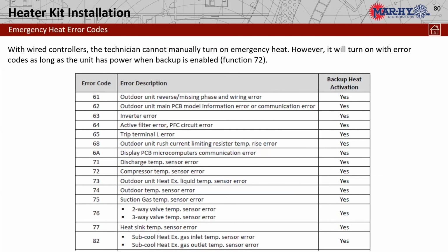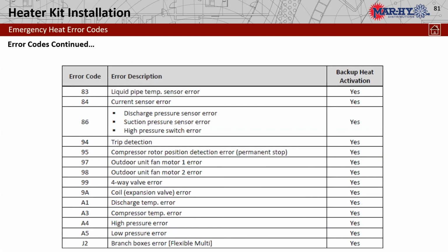So we talked about the emergency heat coming on during any of the outdoor unit lockouts, and any one of these error codes that you see will initiate that function. Anytime it sees these error codes, it will automatically convert to strip heat operation. And there's quite a few of them. Let's hope we never see them, but it is kind of nice that it's an automatic function.